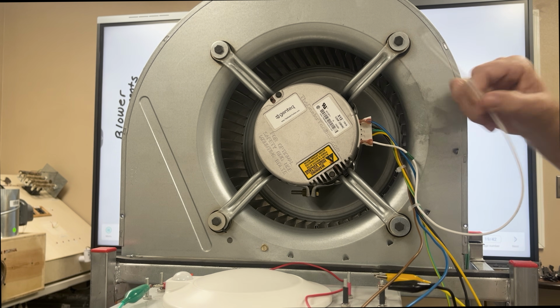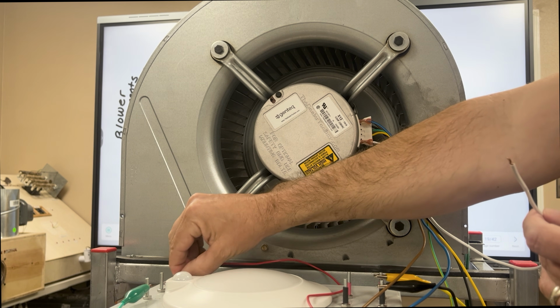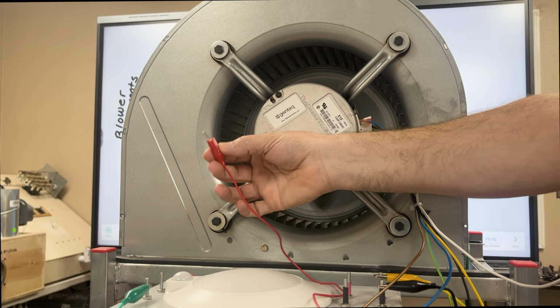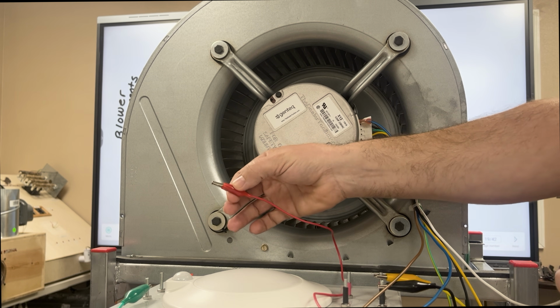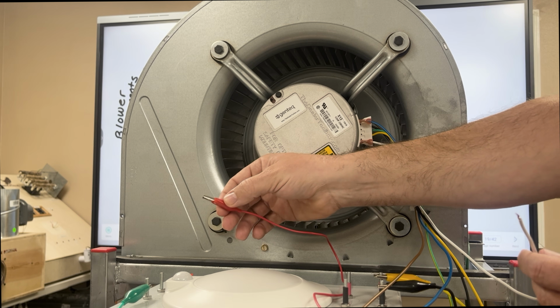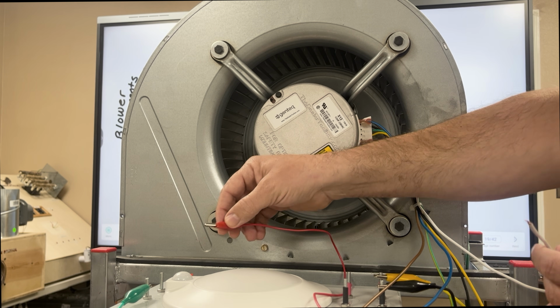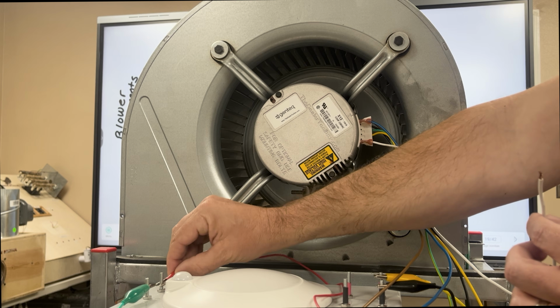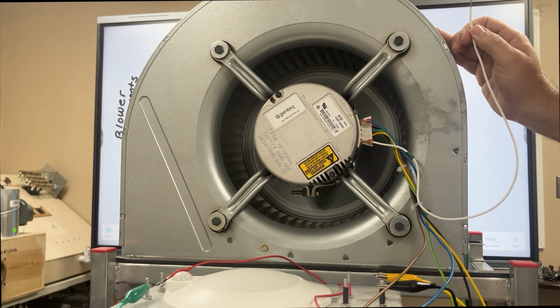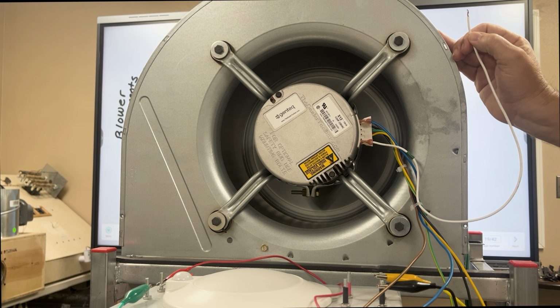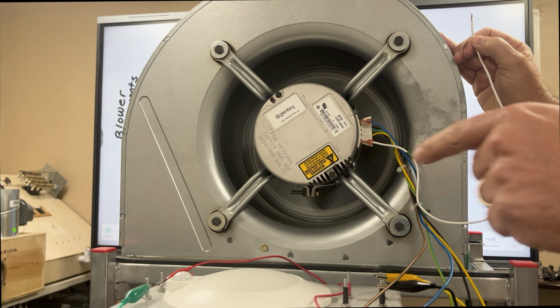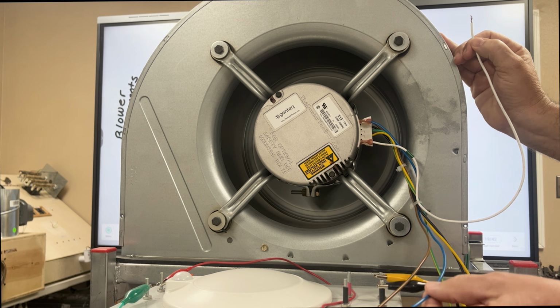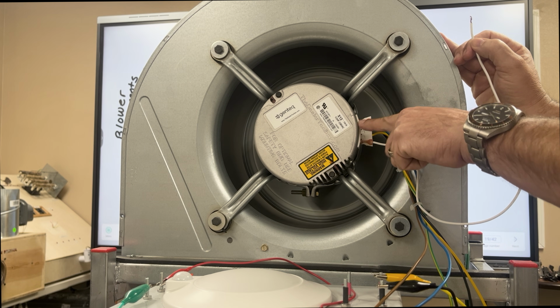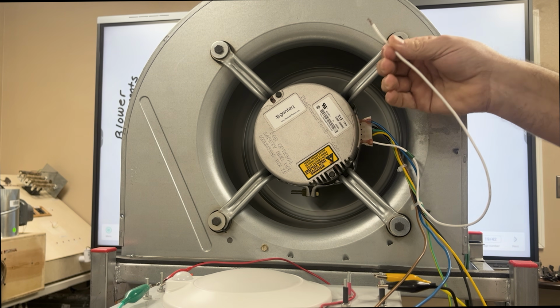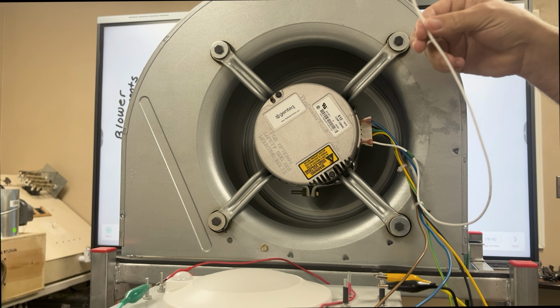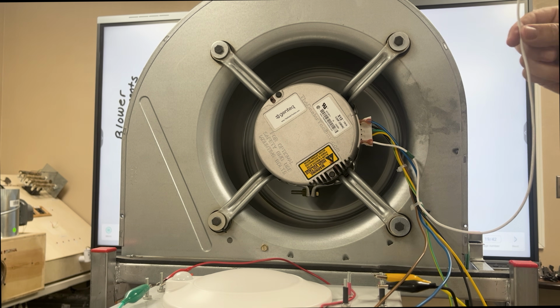And we'll go ahead and turn it on. Matter of fact, I'm going to just remove power from my transformer so the motor will not run. Now that the breaker's on, we have live 230. I'm going to connect 24 volts. As you can see, the motor's coming on, it's running. The only thing this is wired to is my blue wire, which is connected to terminal 1, which is low speed. I have my white wire, which is connected to terminal 5, which is high speed.